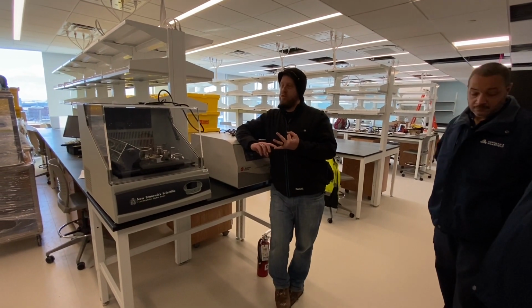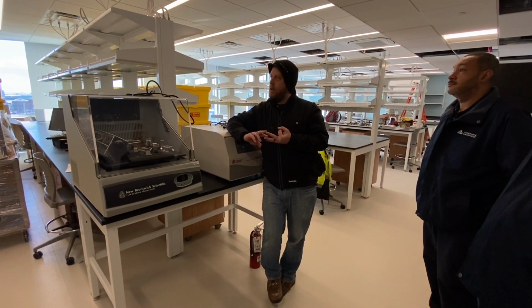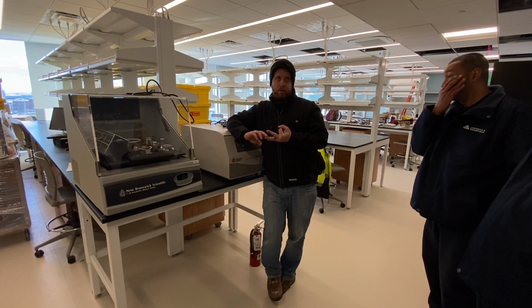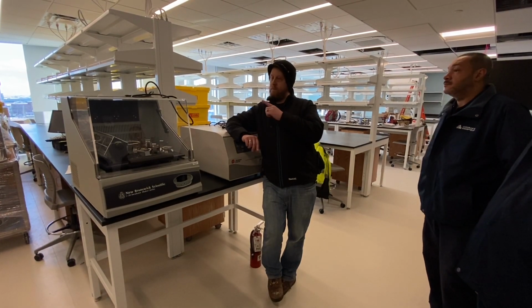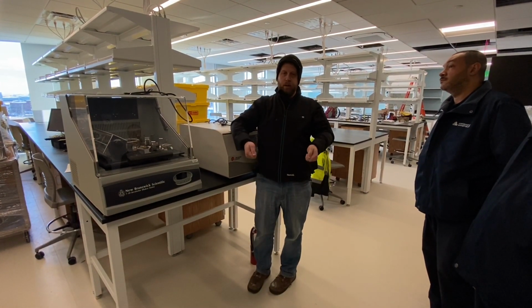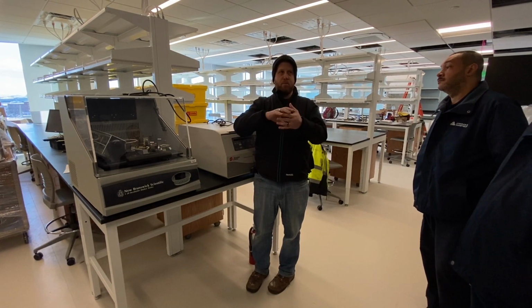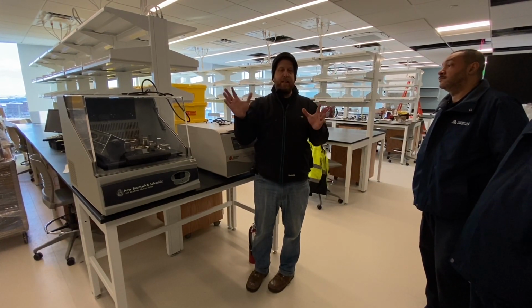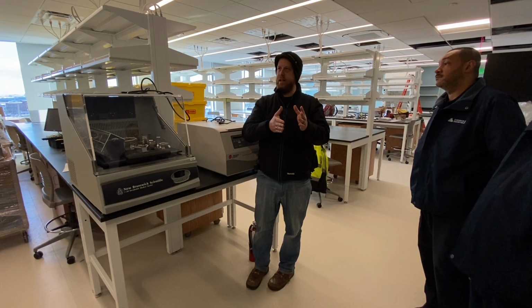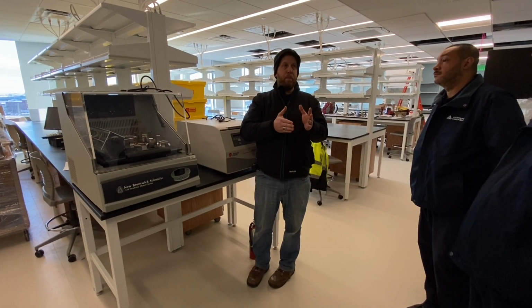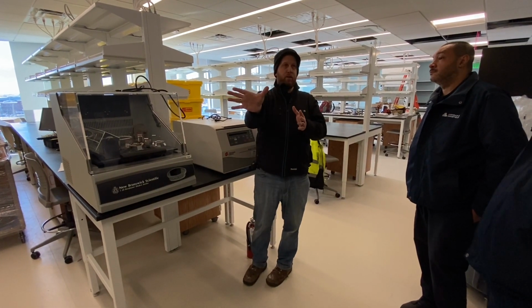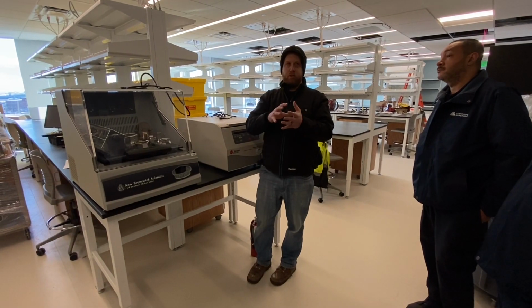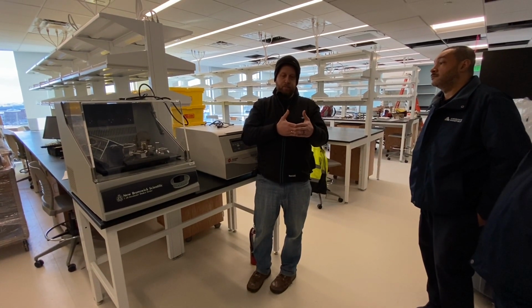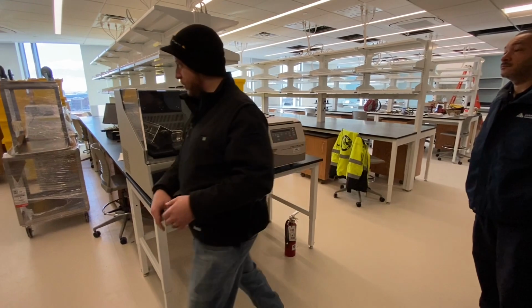So the supply air is constant. The fume hoods open and close based on the sash position, so you open up a sash and it requires more, it controls to the face velocity. You need to get that - Frank, help me - it was 110 feet per minute going into the fume hood. So those make sure they maintain that face velocity. Let's walk over there and show you guys a little bit.